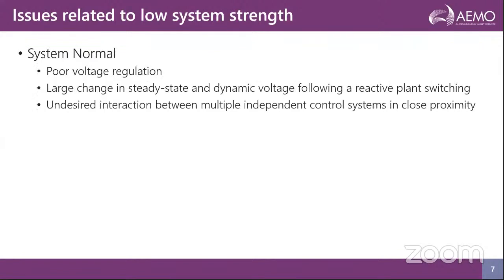So what are the issues? In day-to-day operation, like system normal, low system strength can result in multiple undesired system performances, such as poor voltage regulation, potentially leading to excessive voltages, violating steady state limits. Brian mentioned a simple example of that, which was observed during the connection process. When a reactive power plant is switched in, it can result in a larger than expected voltage change. And this could result in undesired or sometimes unstable interaction between fast control systems that are within close proximity to each other. It may happen that a small change in the power flow condition could lead to a localized voltage collapse in that area when the system strength is low.